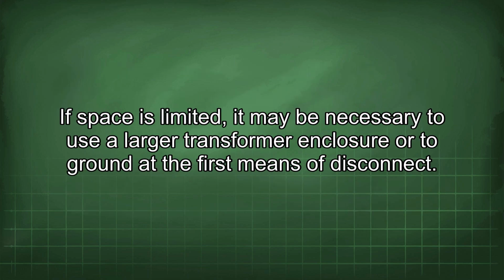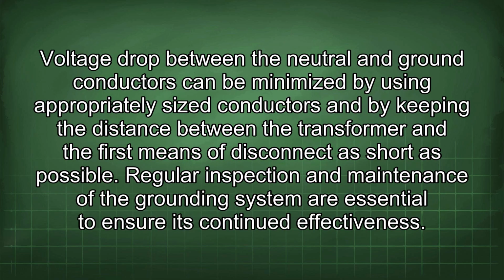If space is limited, it may be necessary to use a larger transformer enclosure or to ground at the first means of disconnect. Voltage drop between the neutral and ground conductors can be minimized by using appropriately sized conductors and by keeping the distance between the transformer and the first means of disconnect as short as possible.